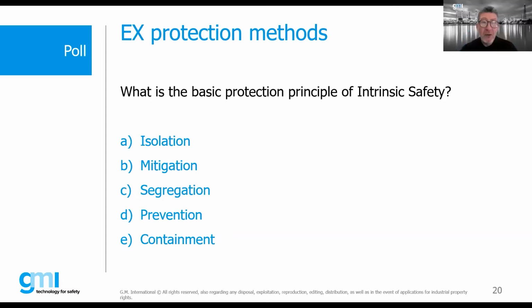If I remember correctly, non-incendive cannot be used in some area classifications, it has limitations, no? Yes, non-incendive is approved for Class 1 Division 2 in the United States under the National Electric Code. We cannot use it in Division 1 areas, and it's not a recognized protection concept under the 60079 standards.